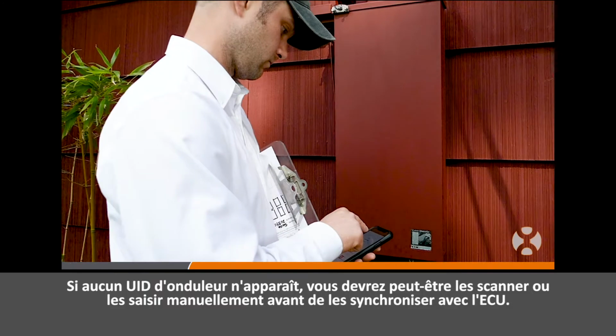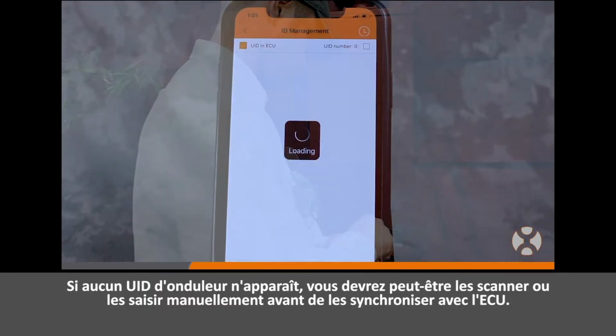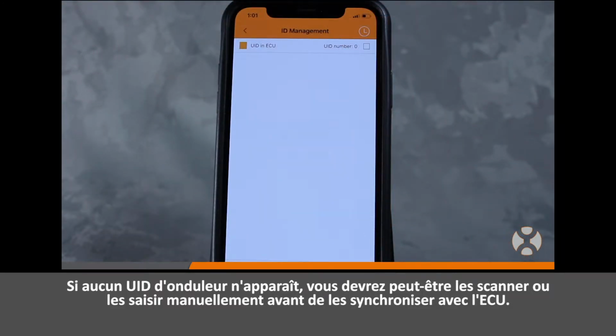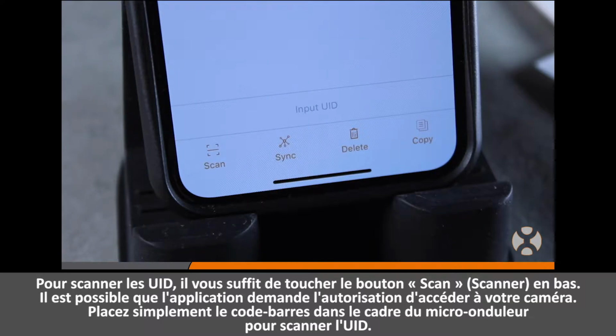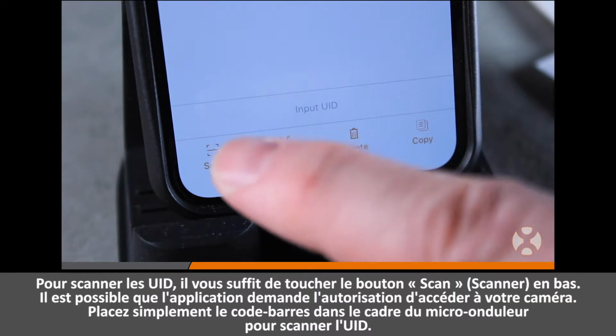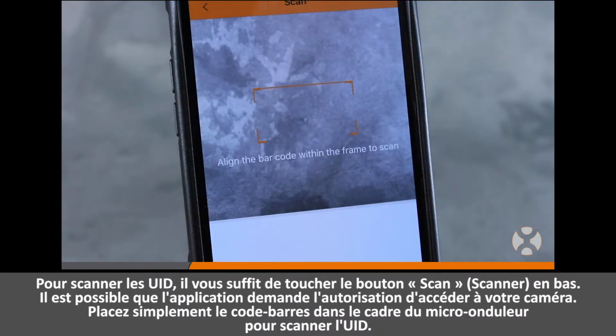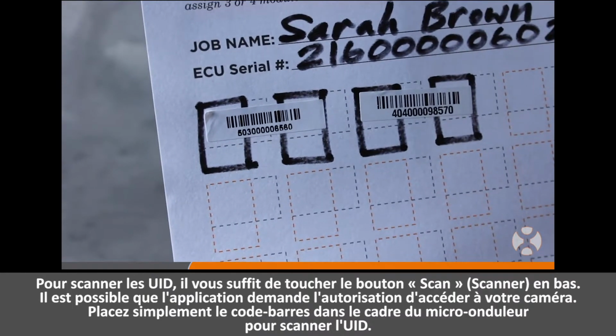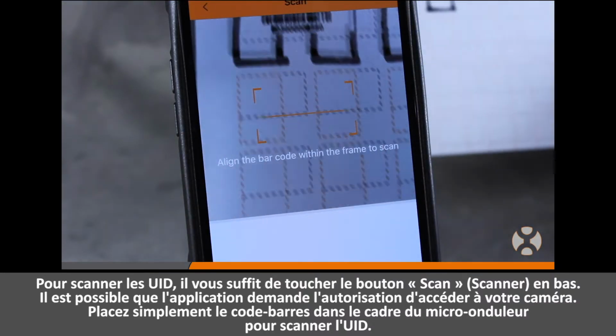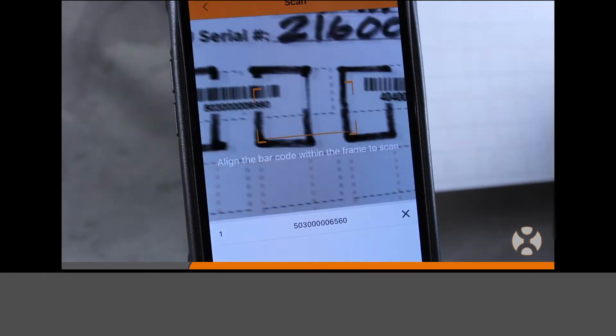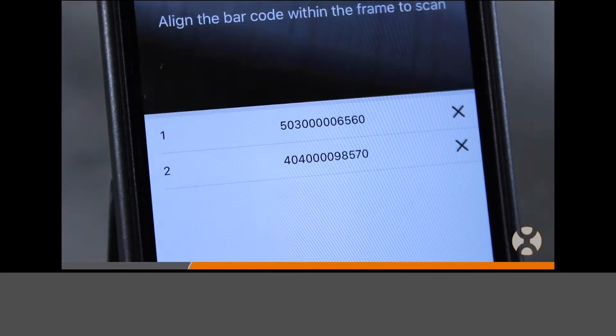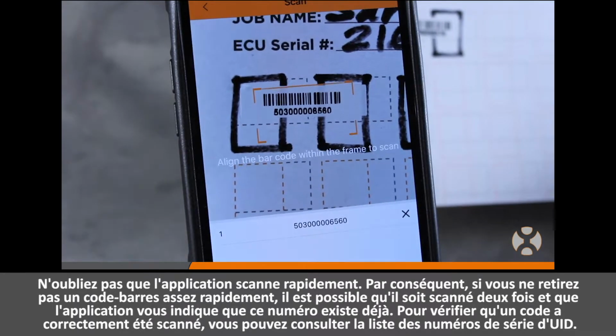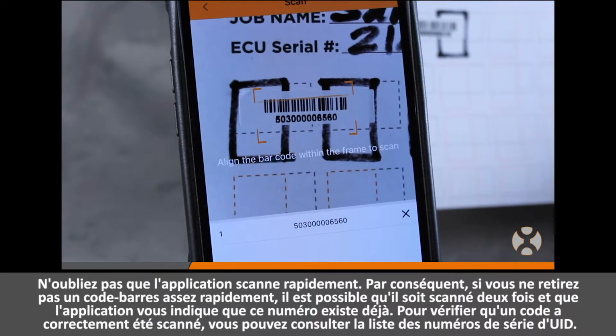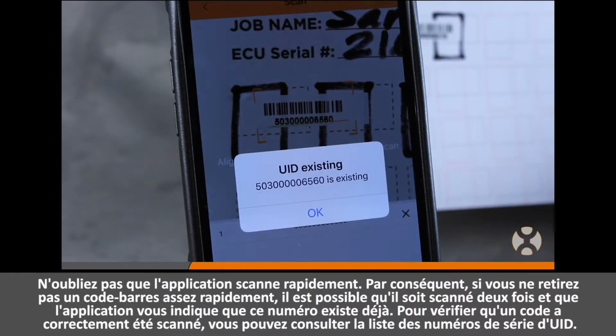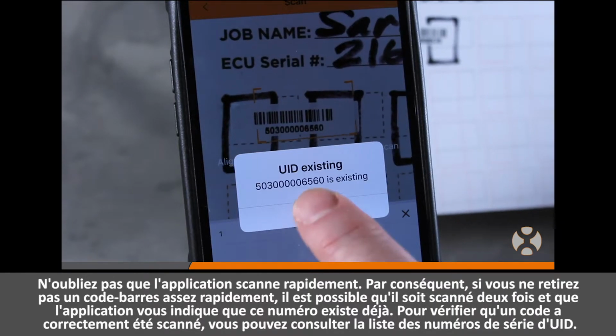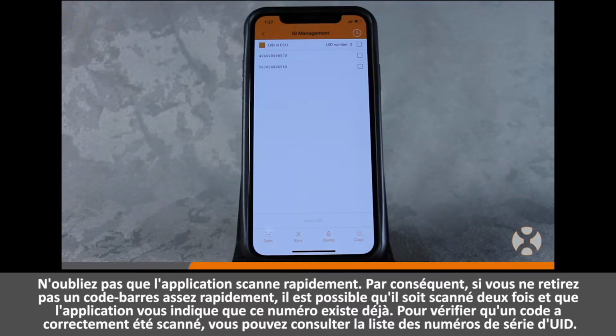If all the inverter UIDs do not appear, you may have to scan or manually enter them before syncing with the ECU. To scan the UIDs, simply touch the Scan button at the bottom. The app may request access to your camera. Simply align the barcode on the microinverter within the frame to scan the UID. Bear in mind the app scans quickly, so if you linger on a barcode, it may scan it again, and then tell you the number already exists. You can verify a successful scan by looking in the list for the UID serial numbers.